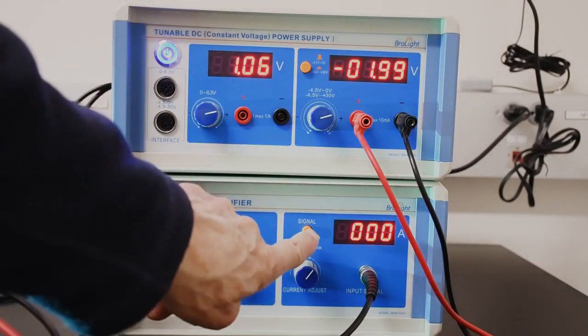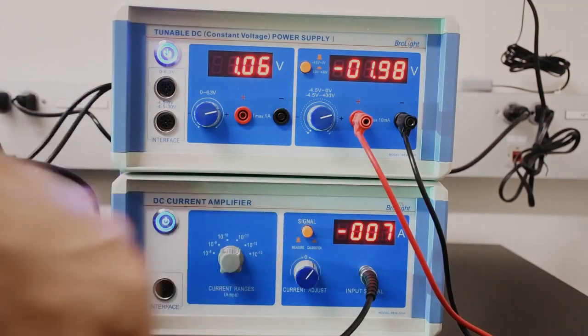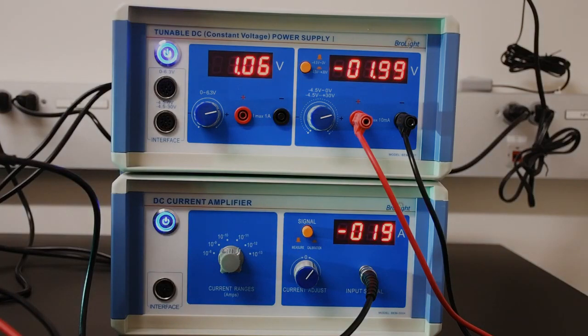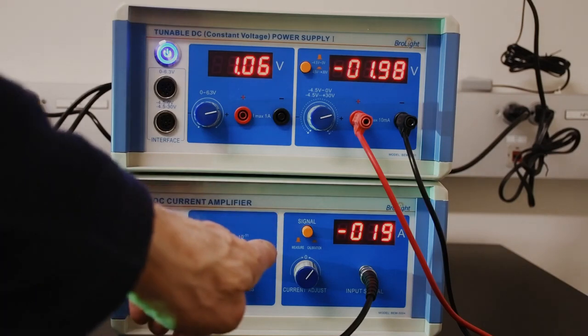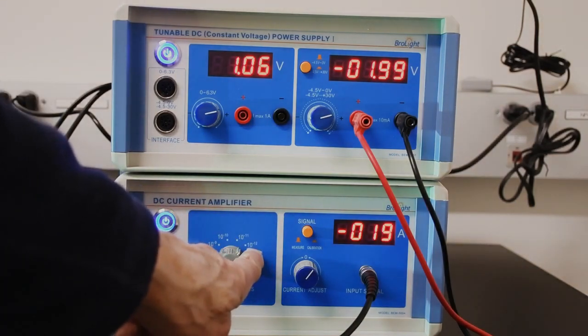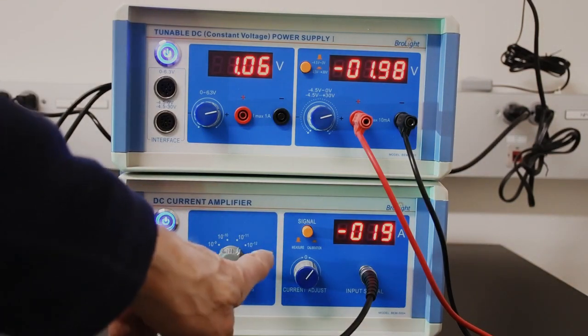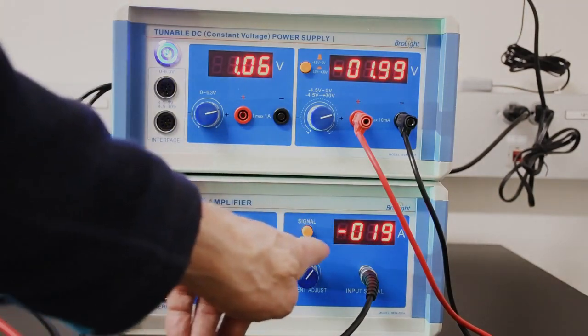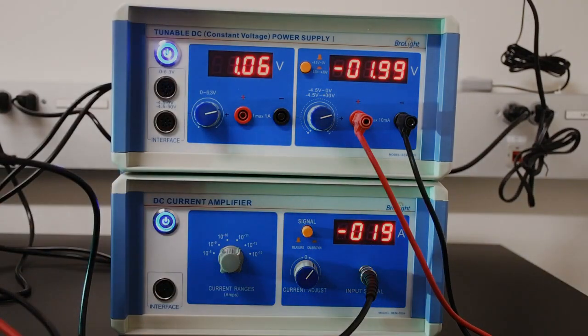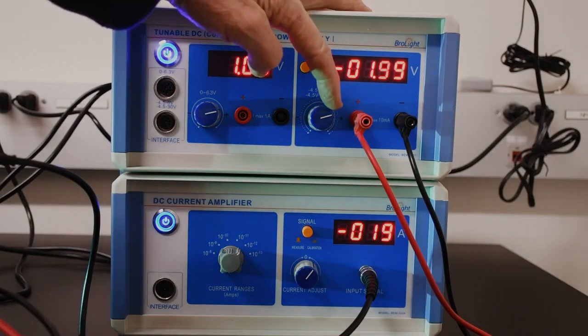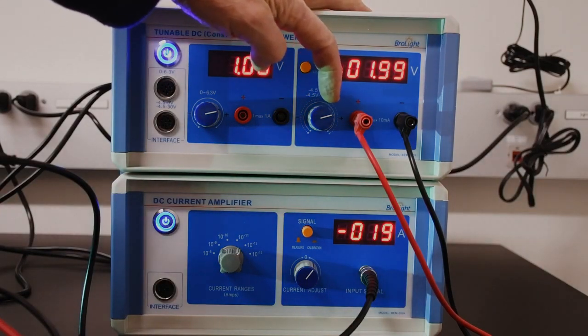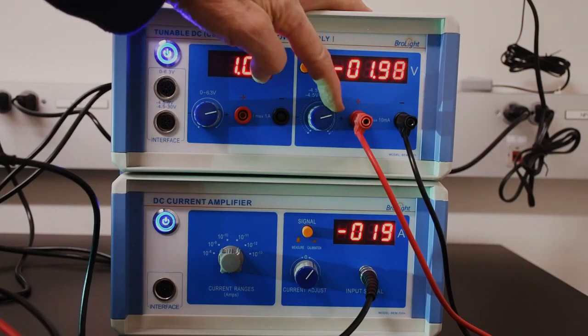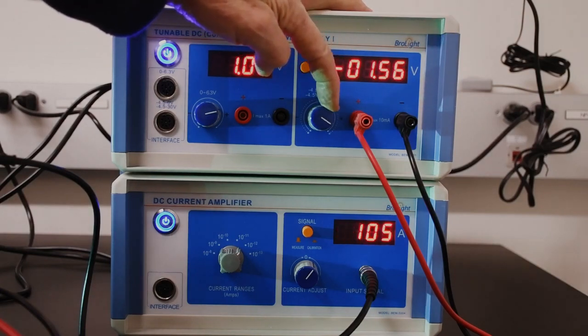Right now it's calibrated at 0. I'm going to undo the calibration. And we'll see a little current there which measures 19 on the scale. The scale is actually 10 to the minus 12, so this is in amperes. We're measuring 19 times 10 to the minus 12 amperes, minus sign on there. So if I change the voltage, you'll see that current change. This is a voltage of 1.99, or nearly 2 volts. So I'm going to reduce it, and the current goes up.